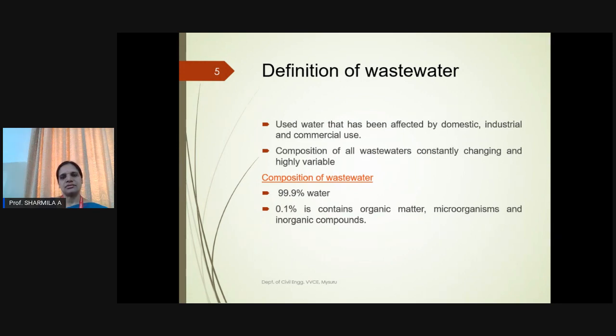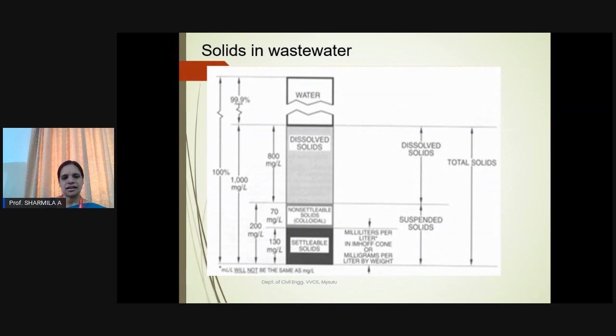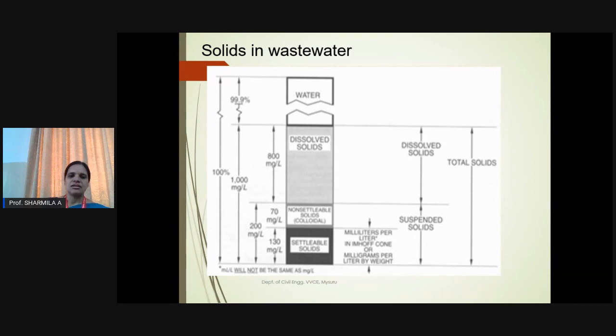Wastewater comprises 99.9% water and 0.1% organic matter, microorganisms, and inorganic compounds. If we take that 0.1% as 1000 mg/L: 800 mg/L will be dissolved solids, which are very difficult to remove and require high-degree treatment. The remaining 200 mg/L can be categorized into 130 mg/L as settlable solids and 70 mg/L as non-settlable solids, and the treatment method varies accordingly.